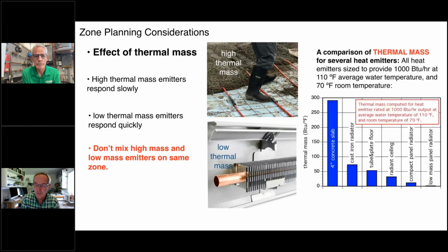And here's just an example. This bar graph gives you a relative comparison between the thermal mass of different emitters. And just to put everything on an even keel here, what I did is determine how much of each heat emitter is necessary to provide 1,000 BTUs per hour at 110 degree average water temperature in a space that's at a 70 degree temperature. And I'm sure it doesn't surprise you, the 4-inch concrete slab is by far the highest thermal mass. And then we start to work down: cast iron radiators, underfloor tube and plate floor heating. And then way over on the right, low mass panel radiators literally are less than 1% of the thermal mass of that 4-inch slab. Both high mass and low mass emitters have pros and cons depending on the situation. But in general, the idea is don't mix them on the same zone.